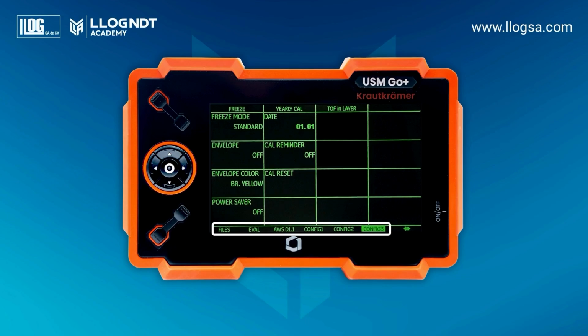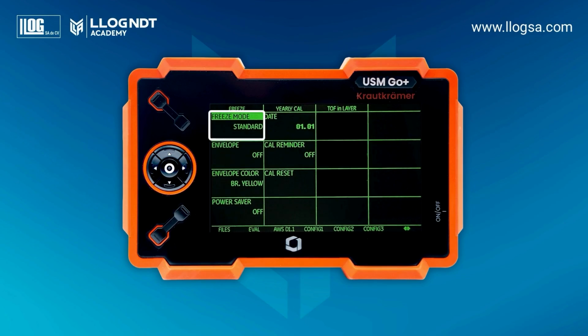The 6th group contains additional configuration functions. The freeze display mode allows you to stop the A-scan manually or automatically when the echo crosses gate A, gate B, or either of the 2 gates. The comparison mode shows a frozen A-scan in the background and the active scan in the foreground. To use any freeze mode, you need to assign the freeze function to function key 1 or function key 2, as explained in the previous group. The envelope function lets you display a frozen A-scan in the background along with an active scan in the foreground. You can also select the envelope color, enable automatic shutdown after a defined period, and set reminder functions for the annual calibration.